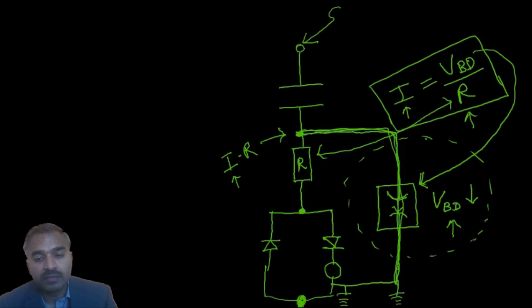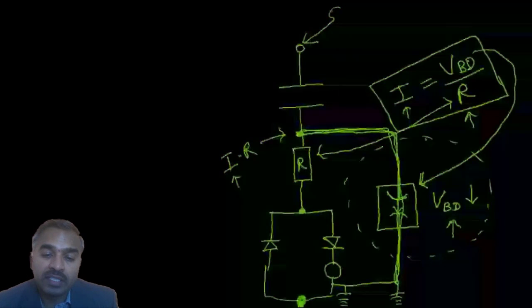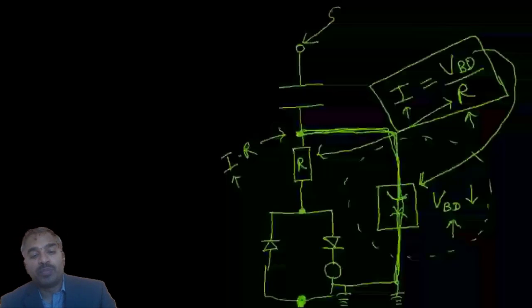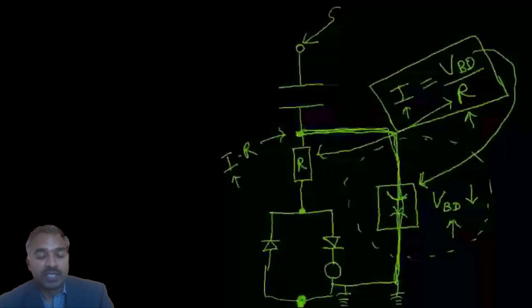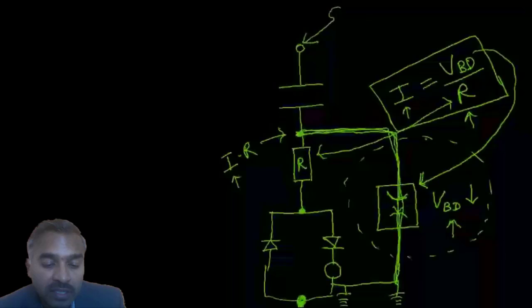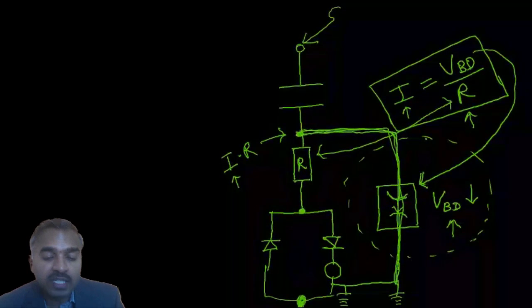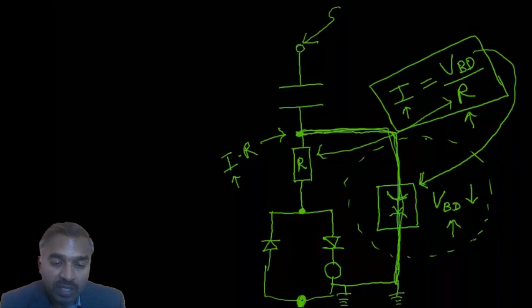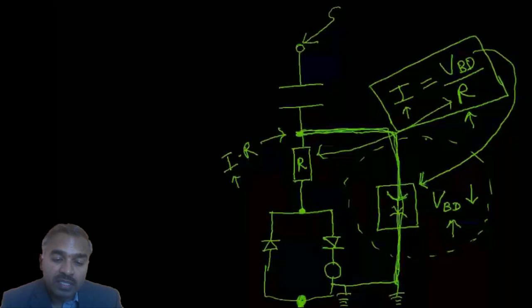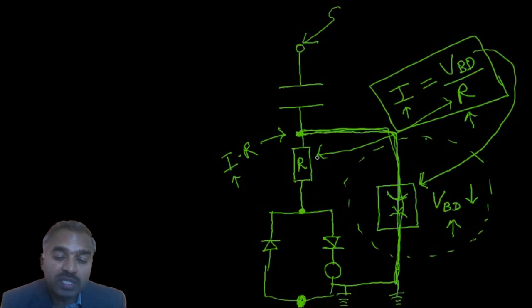So there are two resistors in this system: one for the test object to limit the current, and a second for the measuring instrument to get a voltage. That high resistance connected between the measuring instrument and test object will not protect my diodes. The resistance connected inside this one is especially to protect the diodes and ammeter.